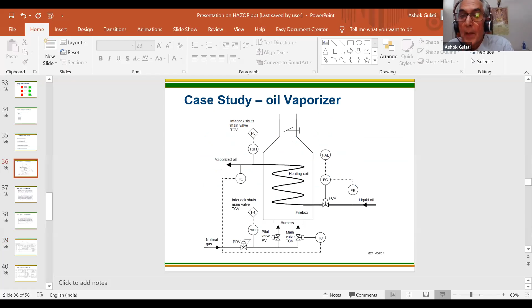The point I want to make is, if we look back, our main recommendation is on this flow: if this flow goes beyond a certain limit, it should trip this valve. My heating must stop if my flow of oil actually stops. Otherwise there will be a problem. So heating must stop, there must be tripping of the TCV, temperature control valve, by a lower limit indicated from FCV. I can take a value from the flow element and trip this. This is what we actually need to do.